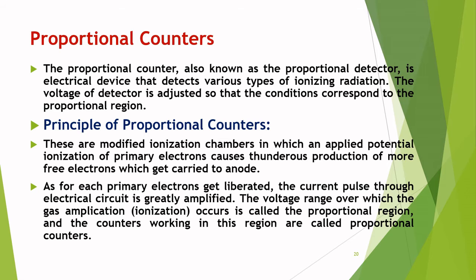Principle of proportional counters. These are known as modified ionization chambers in which an applied potential causes ionization of primary electrons, which causes a thunderous production of more free electrons which get carried to the anode. As for each primary electron liberated, the current pulse through the electrical circuit is greatly amplified. The voltage range over which the gas amplification or ionization occurs is known as the proportional region, and the counters working in this region are known as proportional counters.